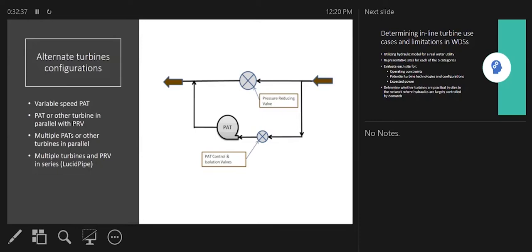There's also the possibility of having a pump as a turbine, or some other turbine, in parallel with a PRV. The PRV acts as a backup system, which again maybe doesn't accomplish replacing the PRV entirely, but makes it last a lot longer. You could also have multiple turbines in parallel, or, as Lucid Pipe did, in series.